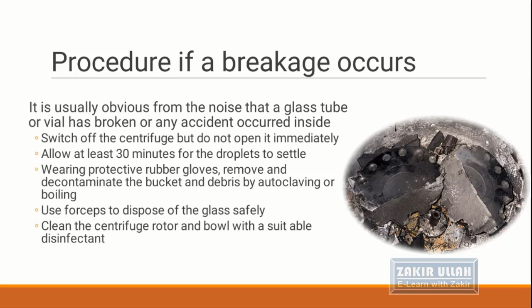Use forceps to dispose of the glass safely. Do not touch the broken glass in the centrifuge with bare hands, but use gloves. Put gloves on your hands, and then with the help of forceps remove the glass or plastic pieces which are present in the centrifuge. Then after removing all the pieces, clean the centrifuge rotor, its bowl or the tube holders with a suitable disinfectant, so that the whole centrifuge is disinfected and all the infectious materials are killed.